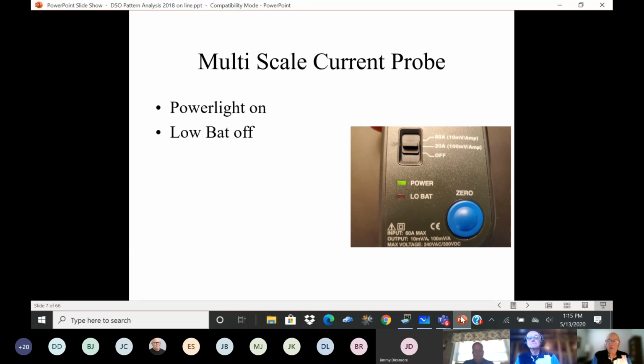Do not ever use a current probe if the battery light is on, because the accuracy is affected as the current probe tries to measure, especially if it's fluctuating. Most of these have 9-volt batteries, and once the battery gets about a third down, you'll start seeing that.